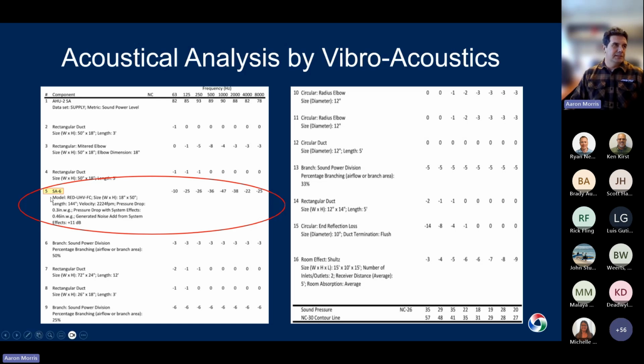So we added this silencer number 6 in this case, which was a supply air silencer that we installed. And then in this calculation, they're showing the insertion loss of the silencer. And on the bottom line, they're showing that, with each octave band, what the resulting sound pressure is going to be, and the resulting NC26, which is below the NC30 target.